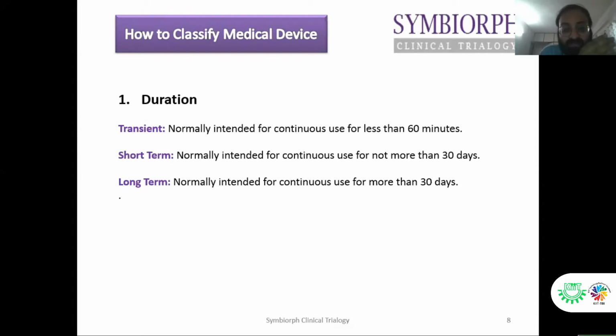If your device is intended for continuous use for less than 60 minutes, then it is a transient use medical device. If your device is used continuously for not more than 30 days, it is a short-term use device. And if it is used continuously for more than 30 days, then it is a long-term device. After you have defined your medical device with its intended use, the second thing is to define its duration of use.